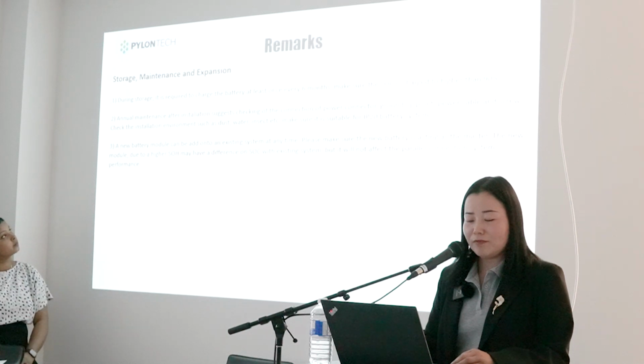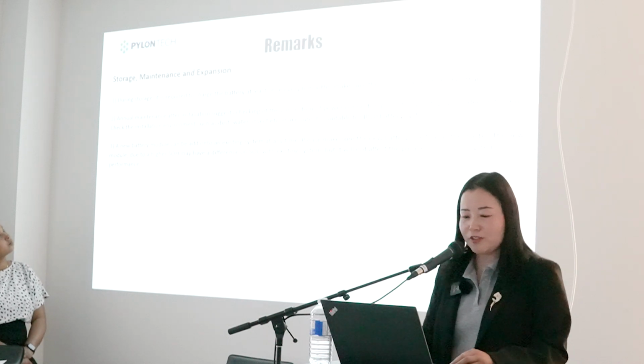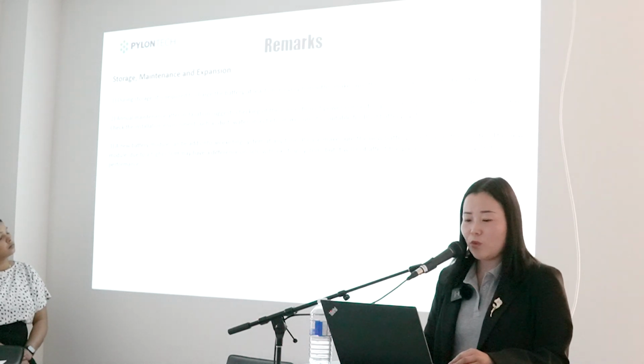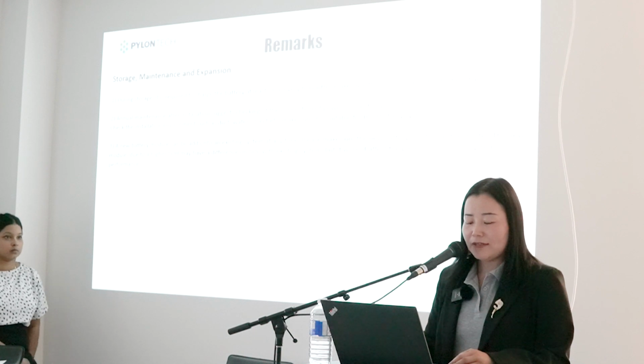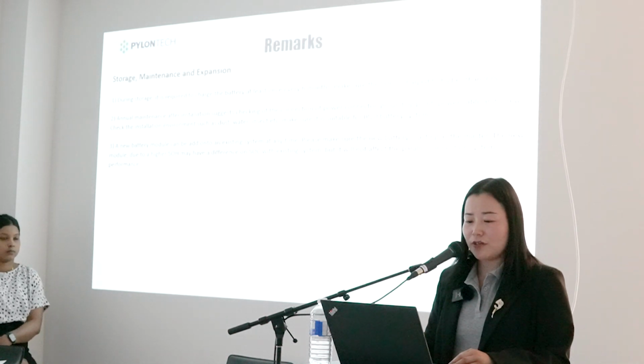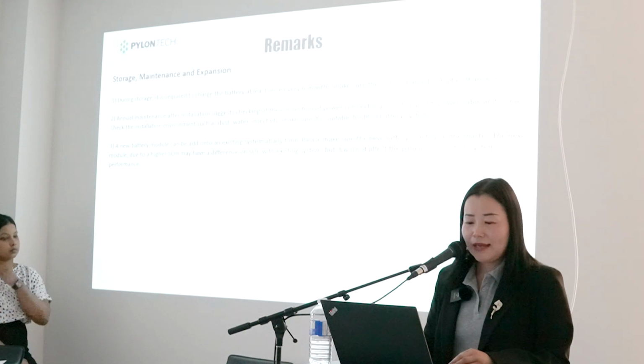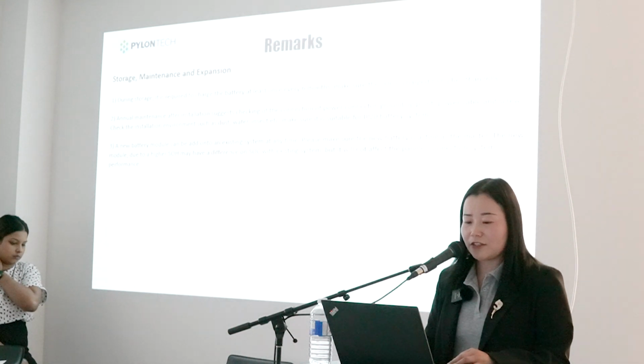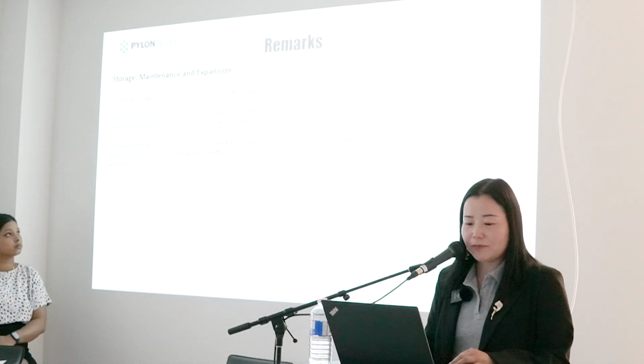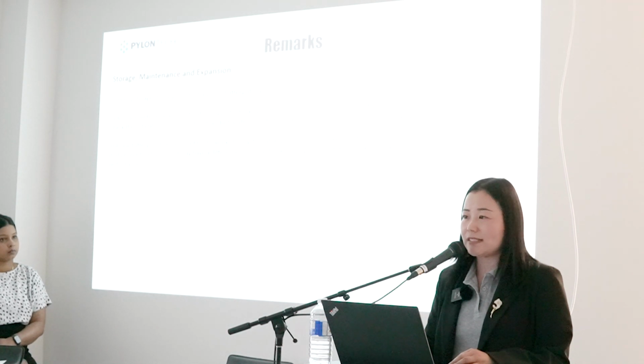So here are some remarks for storage, maintenance and expansion. During storage, it's required to charge the battery at least once every 6 months and make sure the SOC is charged to higher than 90%. Annual maintenance is recommended after installation. And a few battery modules can be added onto an existing system at any time, but please make sure the new battery module is always the master.